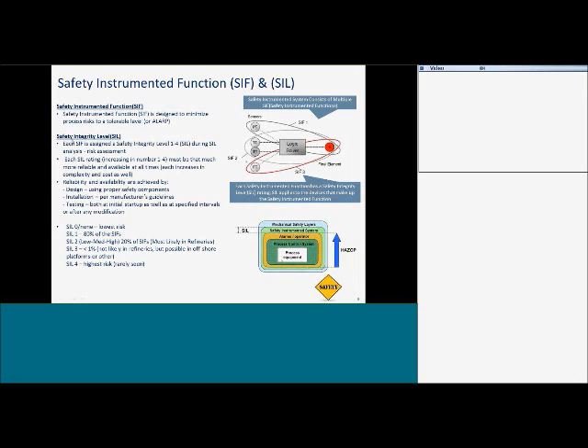Now, SIL stands for Safety Integrity Level. And the SIL levels go from 0, which would be the lowest risk, all the way up to 4, which would be the highest. SIL 4 we call the unicorn in a sense because we don't see it. I've not ever seen SIL 4. However, SIL 3 is somewhat common. We see them in HIPPS systems. We see them in some refinery systems. SIL 3 is the highest that we're seeing in industry today. And each one of these, SIL 1, 2, 3, goes up in order of magnitude more reliable than the previous level. So each level that we go up is becoming an order of magnitude more reliable.